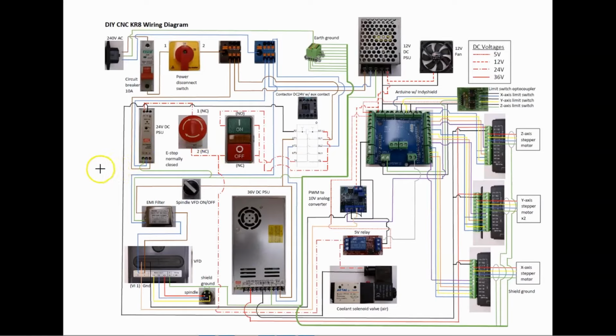On the lower left corner, we have AC supply to both the VFD and the 36 volt PSU. Remember, the AC supply to both is controlled by the contactor. So in case there is a power outage, the AC power to both the power supply and the VFD will be cut off, and it can only be turned on again by manually pressing the on button or releasing the e-stop and pressing the on button.